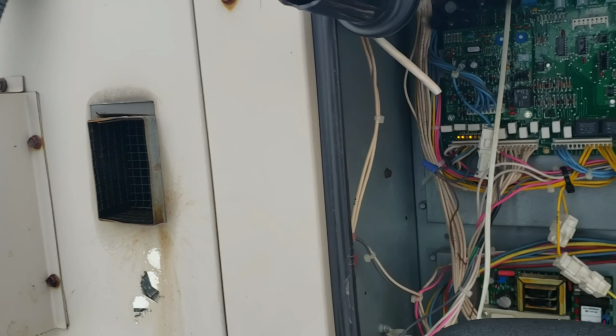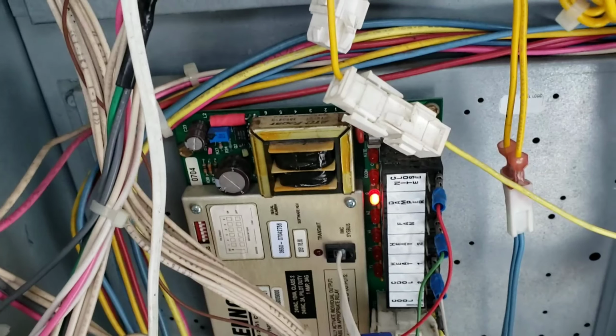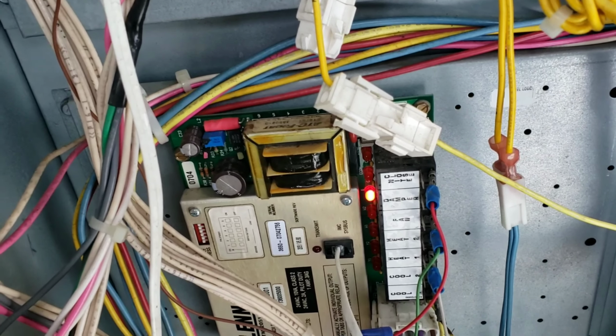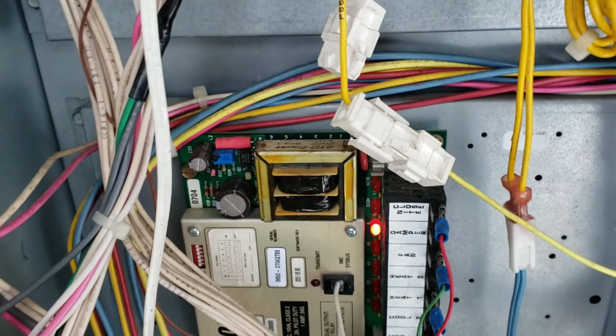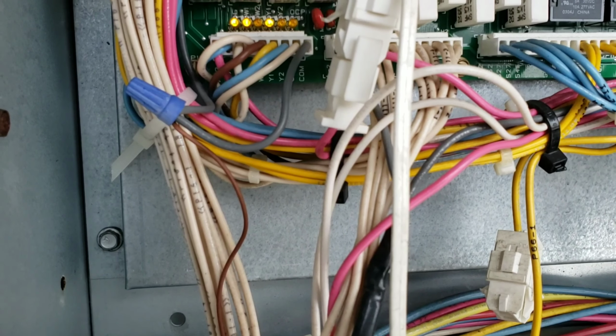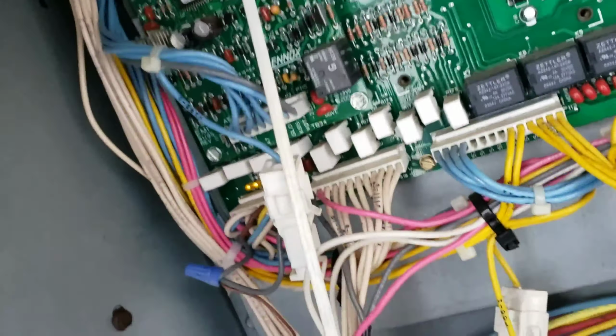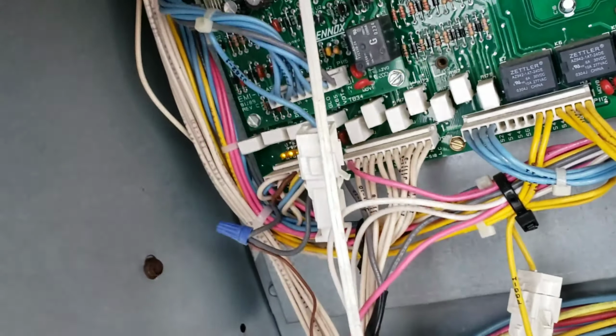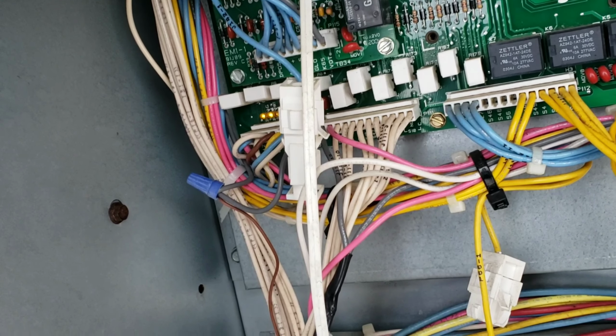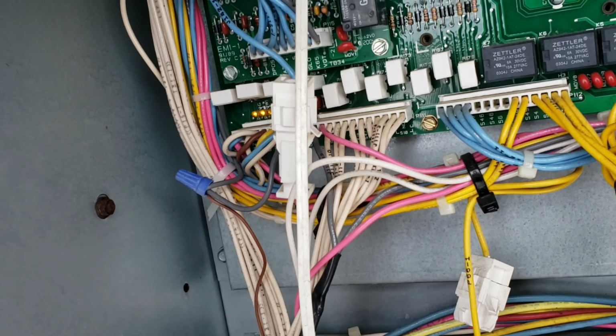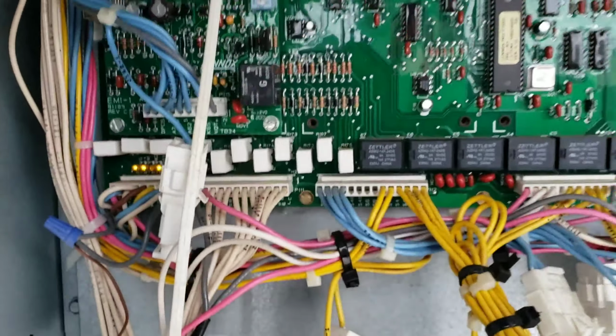This unit has a board on it, and I'm not seeing where it's calling for more than one thing. Even up here, it is calling for air conditioning and heating at the same time. I know it's kind of hard to tell with that. So we're going to figure out why this is telling it to run both. It won't do any good to just reset it, because I believe it'll do the same thing again.